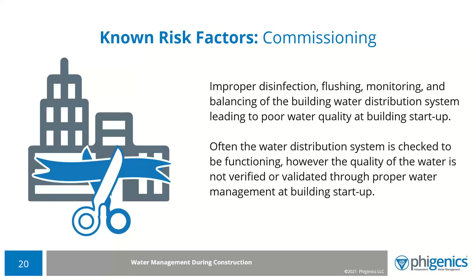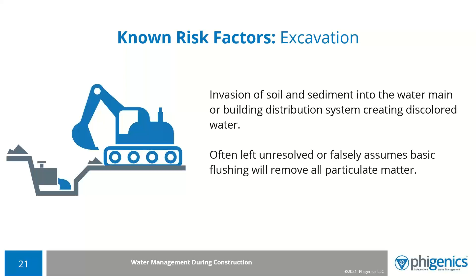The second risk factor is excavation. A lot of folks don't know that soil and sediment actually contain pathogens of interest. They may be in a dry format, and they can become airborne or can contact a water reservoir or moisture source. A lot of folks in construction just say it's discolored water, we'll just flush it through the system. But all that particulate matter and organic material can get caught up in a system in very fine particulate matter, and it can add to the growth and spread of a pathogen. We want to reduce that. It's not appropriate to just wait until it clears and assume that water is safe. It would be safer, but it doesn't mean that if it was left in the system in a dormant state and you didn't know it was in there, that it would not cause a problem.